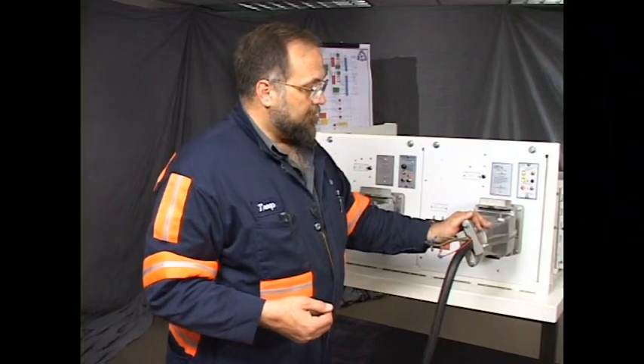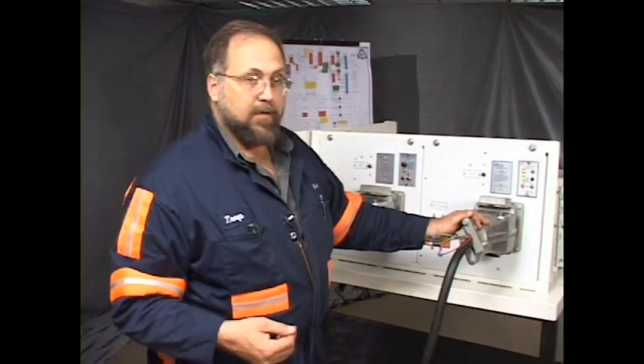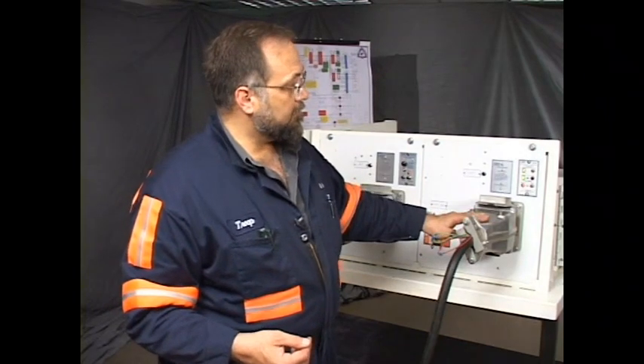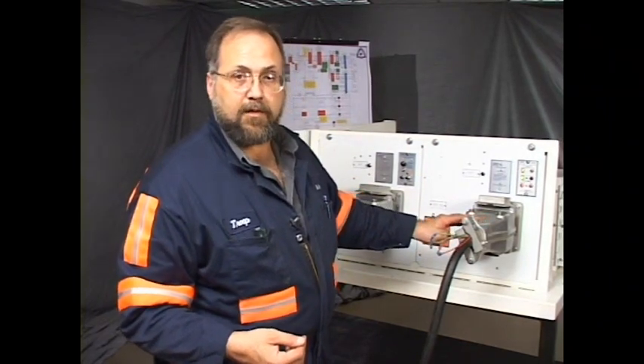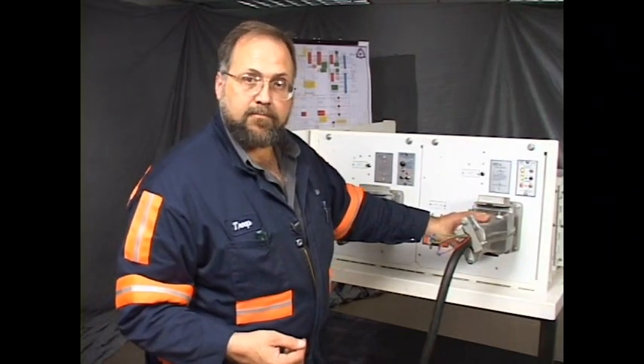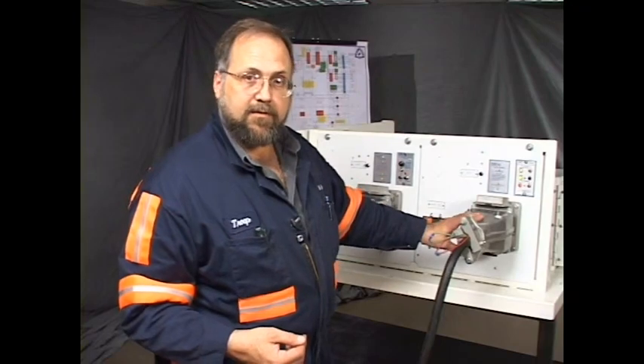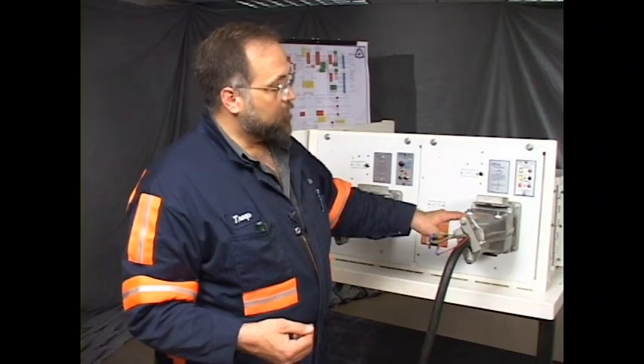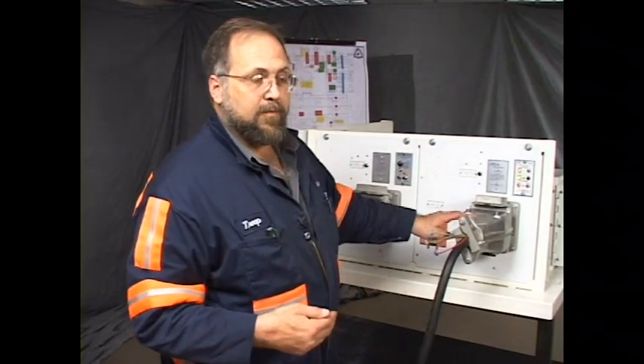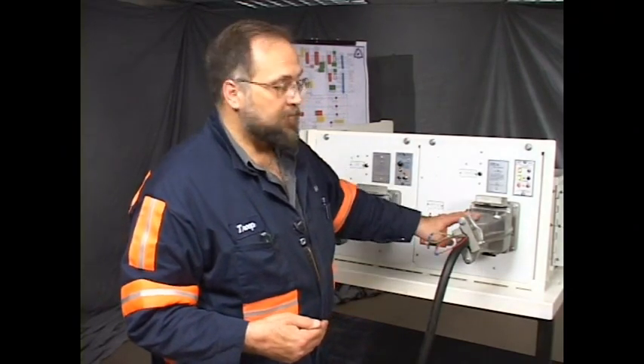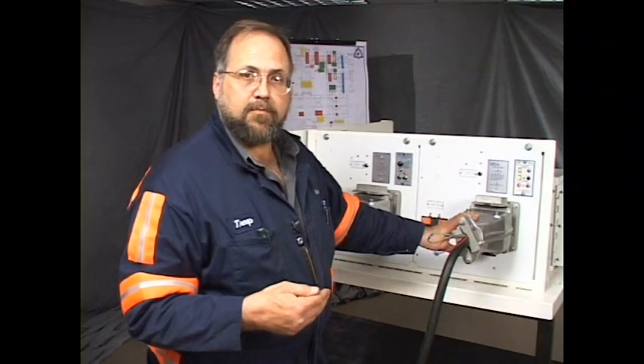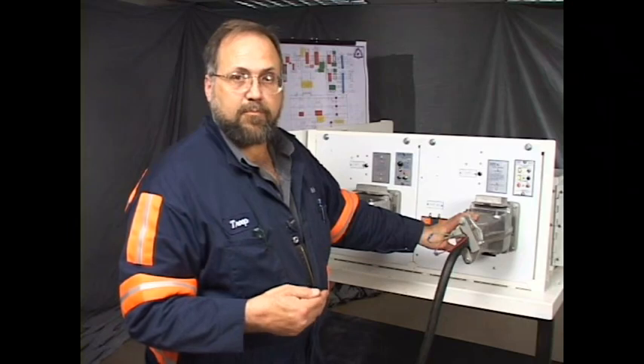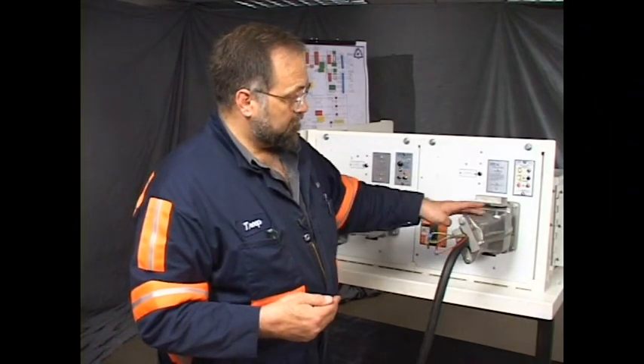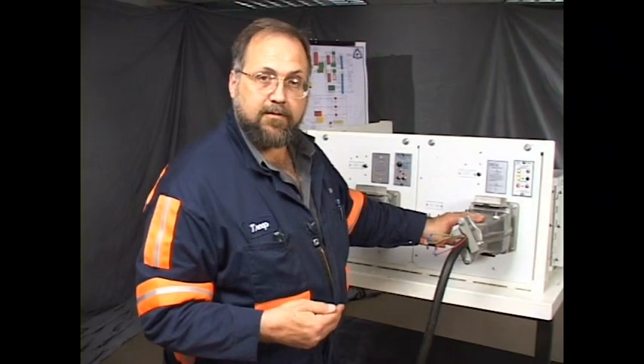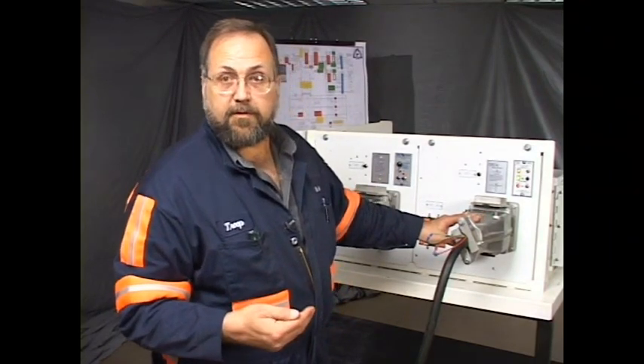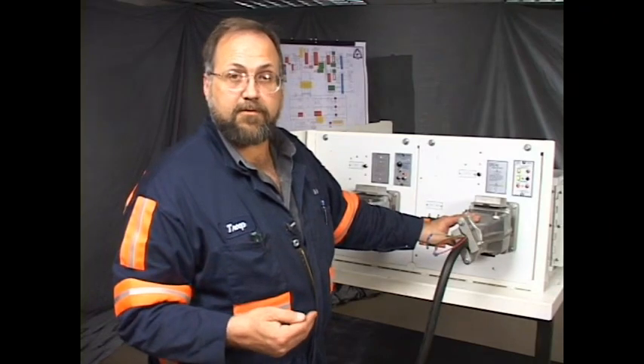In order for this machine to operate correctly, for this system to work correctly, the ground blade inside the cable coupler must be isolated electrically from the shell of the cathead. The shell of the cable coupler can't be connected to the ground blade. The signal must go from the filter, through the ground conductor, through the cathead, through the receptacle, and then be picked off by the CT on the inside to satisfy the monitor. If the signal should by chance come in contact with the shell of the cathead, of the cable coupler, then the monitor's defeated. It's bypassed, it's tricked.